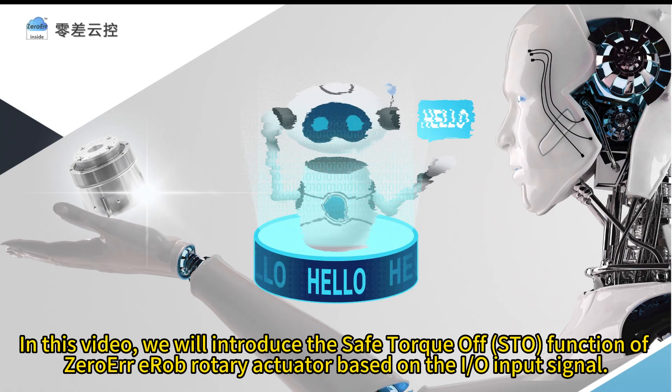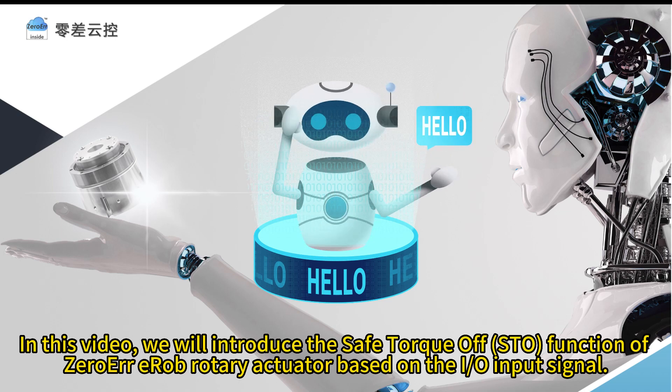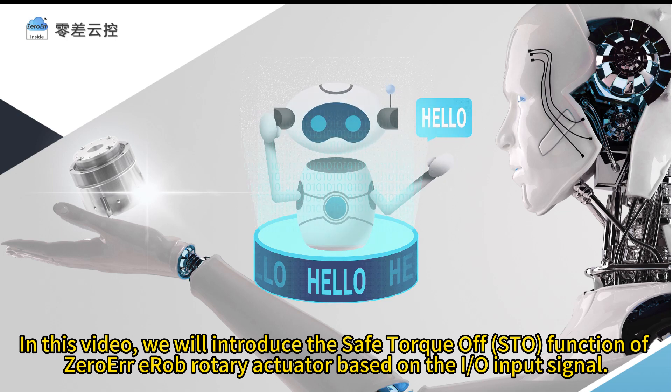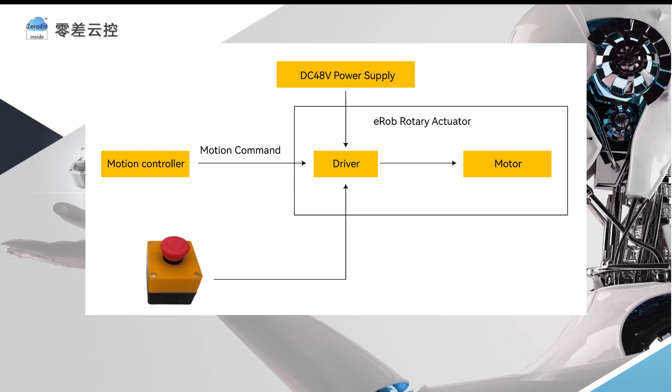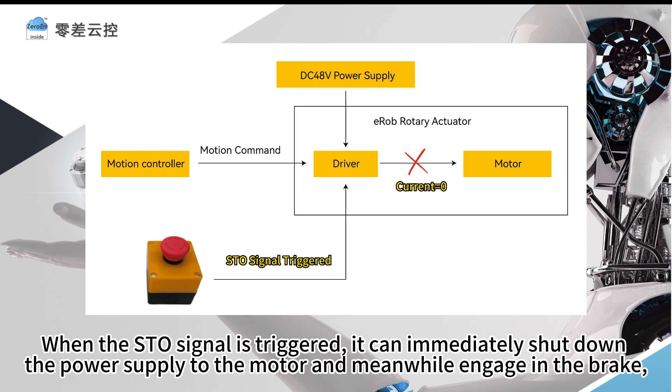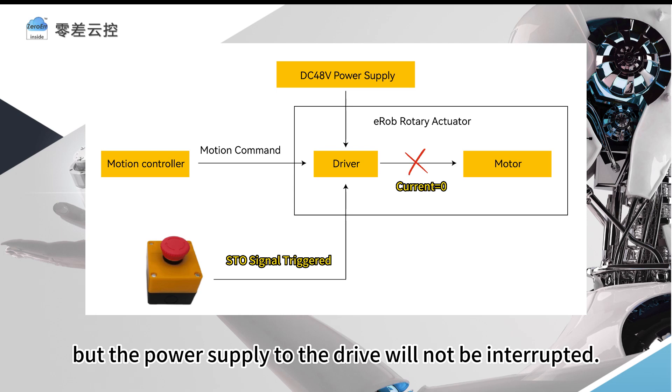In this video, we will introduce the Safe Torque Off function of the ZeroErr eRob Rotary Actuator based on the I.O. input signal. The Safe Torque Off function is used in emergency stop situations and accidental starting prevention situations. When the STO signal is triggered, it can immediately shut down the power supply to the motor and meanwhile engage the brake, but the power supply to the drive will not be interrupted.